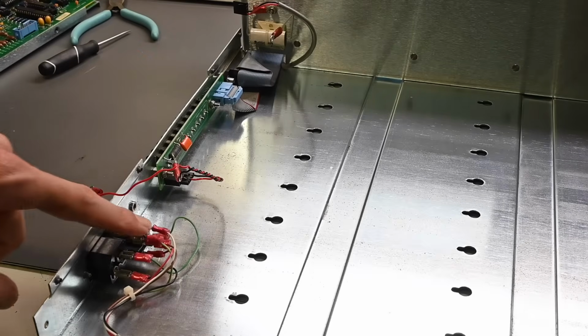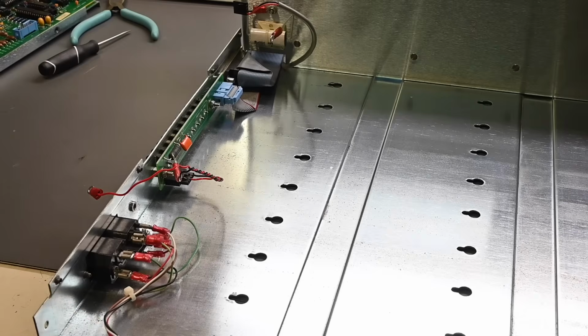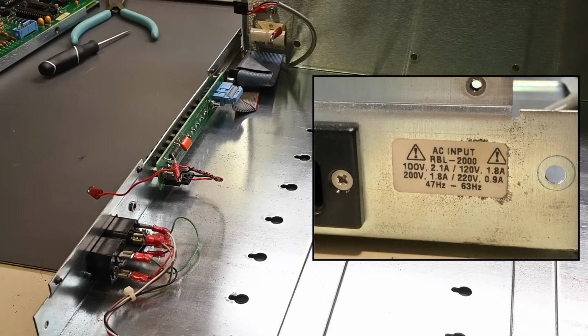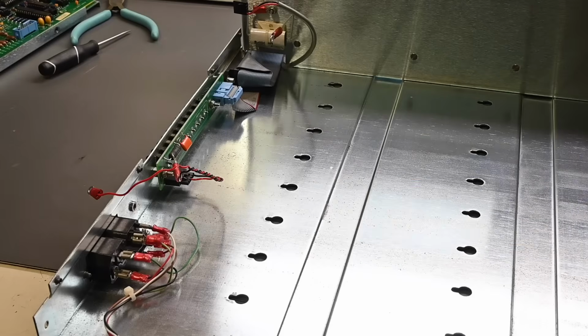You can see the AC wiring coming in right here is not all that large, but that's to be expected because this doesn't require that much power to actually operate. You know, there's some power, about 15 watts or so, to operate the fans and then obviously the electronics. But again, not that much is required. There's a tag on this back corner and it says 100 volts at 2.1 amps, 120 volts at 1.8 amps, 200 volts at 1.8 amps, and 220 volts, 0.9 amps, 47 hertz to 63 hertz. So, a fairly low amount of power actually to operate this electronic load.